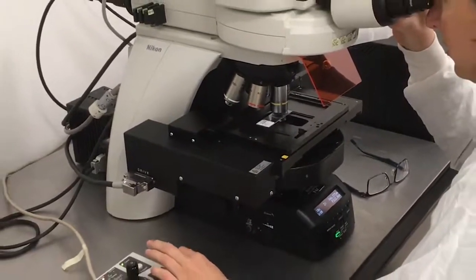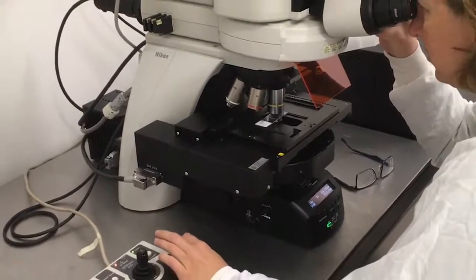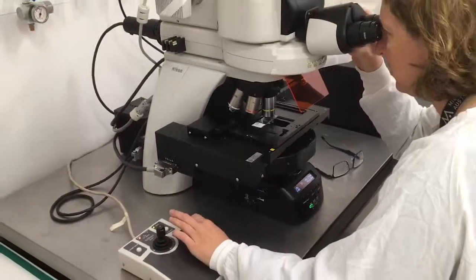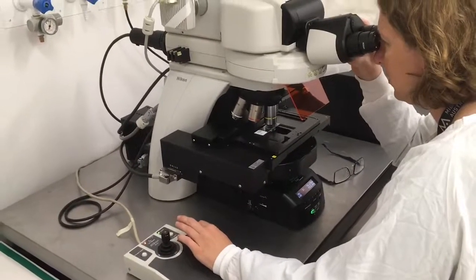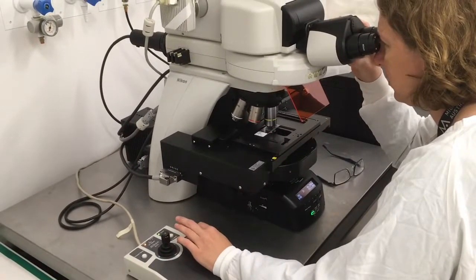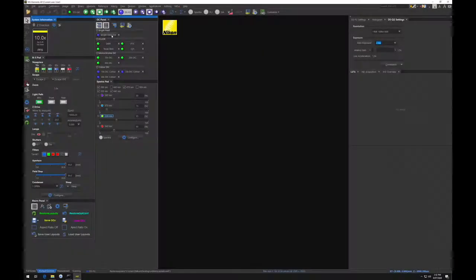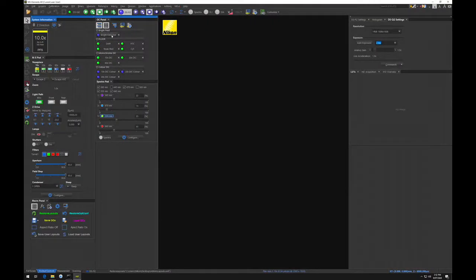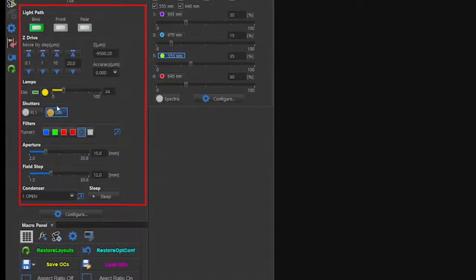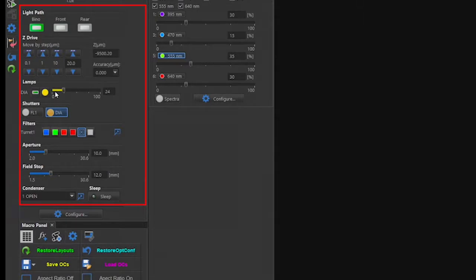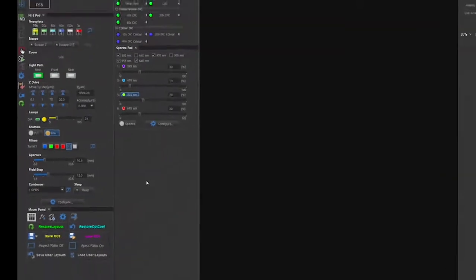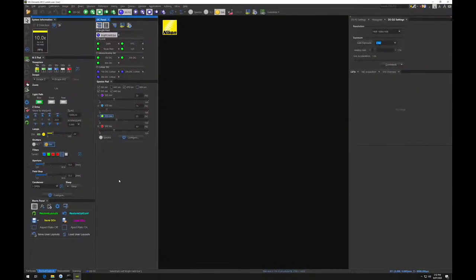Now look down the eyepiece and start lowering the stage until your sample comes into focus. If you don't see any light down the eyepiece, first check that you chose the correct OC. Reload default OCs and make sure to choose the Brightfield OC. Then make sure the lamp is turned on and the diascopic shutter is open, and the light is being directed to the eyeport. You should see light on the sample.